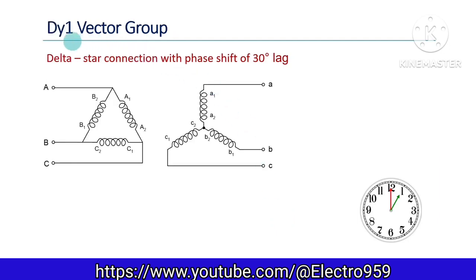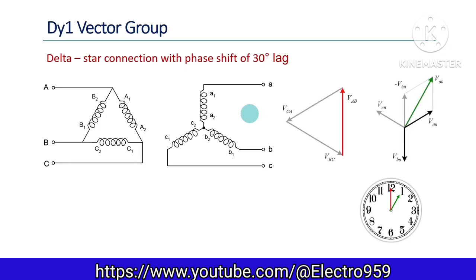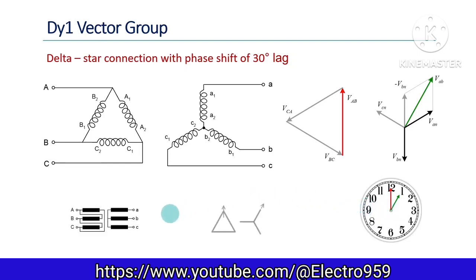Now the DY1 vector group. The primary is delta connected and the secondary winding is star connected. Since line voltage VAB is taken as reference for the primary side, VAB must be considered for the secondary side also. In the star-connected secondary, VAB is obtained by VA minus VB, and the VAB phasor is obtained as shown. Here also the secondary voltage is lagging by 30 degrees from the primary side — the one o'clock position applies here as well. The simplified connection diagram and displacement diagram clearly represent the delta-star connection and the 30-degree lagging phase angle.